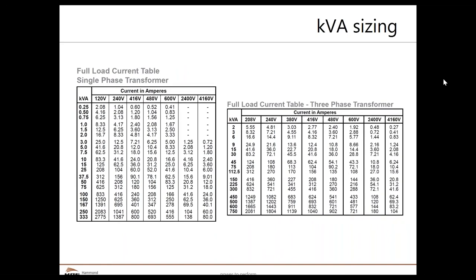This is a quick guide — a full load current table. On the left side you see the single-phase table, and on the right side the three-phase table. This table uses the mathematical formula from the previous slide. You can keep this guide handy for quick reference. It has common kVAs and voltages with their corresponding amperes. For example, a single-phase 240-volt 100 kVA transformer has a full load current of 416 amperes. Similarly, for a three-phase 480-volt 75 kVA transformer, the full load current is 90.2 amperes.